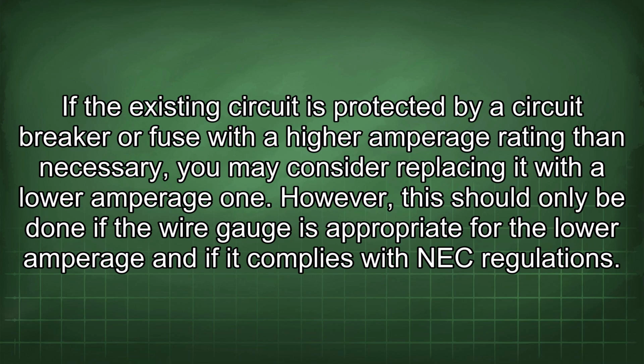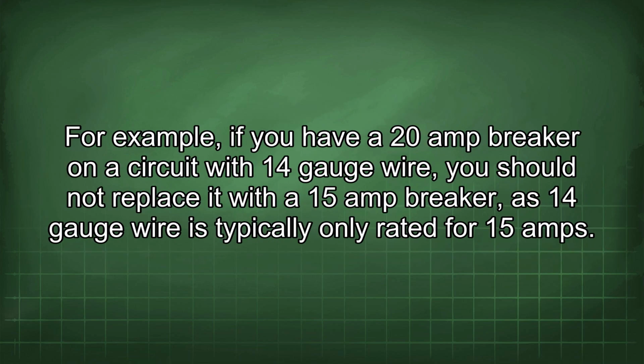However, this should only be done if the wire gauge is appropriate for the lower amperage and if it complies with NEC regulations. For example, if you have a 20 amp breaker on a circuit with 14 gauge wire, you should not replace it with a 15 amp breaker, as 14 gauge wire is typically only rated for 15 amps.